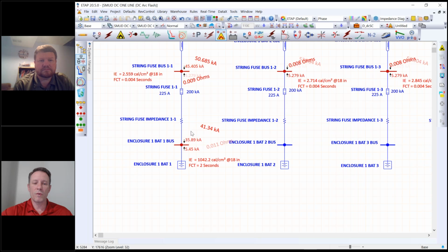In our spreadsheet, what we would have done is take this 35 kA of fault, we would have run that at the time that these fuses take to clear and got the arc flash from that side, which would be probably negligible. It'd be under 1 cal. And then we'd run this 5 kA for the 2 seconds to see what that is, and then add the two numbers up. And this number would dominate that, and it would probably be somewhere around 30 to 60 cal.